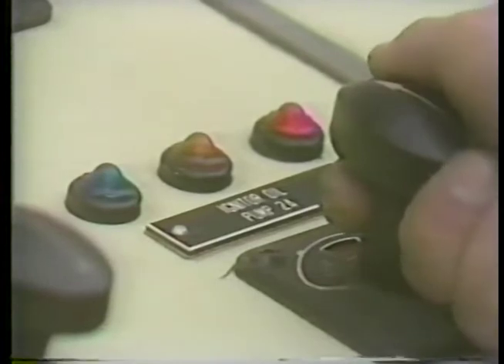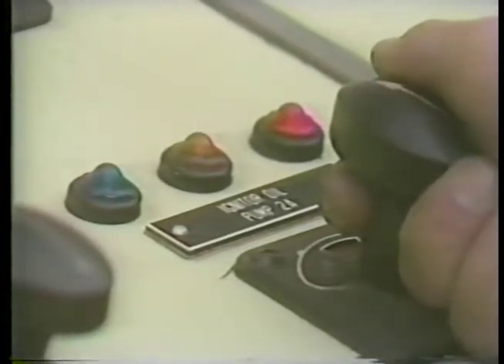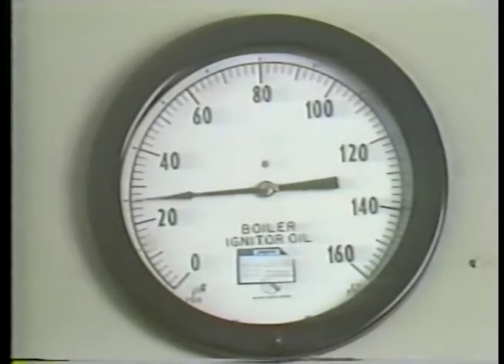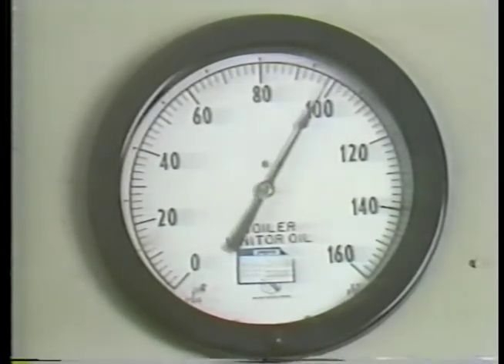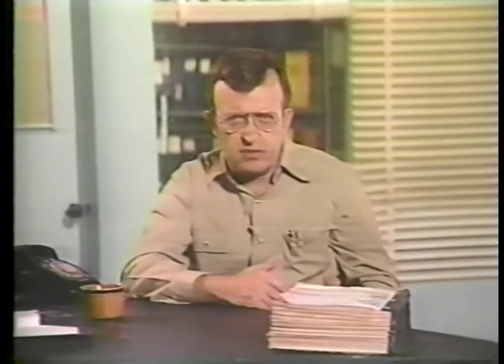With the igniter sparking, the operator starts the igniter fuel oil pump and opens the air atomization lines so that when ignition oil flow begins, proper mixing between the oil and air will occur. Starting the fuel oil pump also opens the oil supply lines to provide the necessary fuel for ignition. The oil is atomized by the air and ignited by the spark from the igniters. At this point, the operator may have to make fine adjustments of the fuel and airflow so that the igniter flame becomes stable and reliable. These adjustments are normally made in the control room by changing the set points on controls such as these. During the course of adjusting the igniter flame, the operator may make a visual inspection of the furnace area by opening observation doors on the boiler to satisfy himself that ignition is taking place properly.